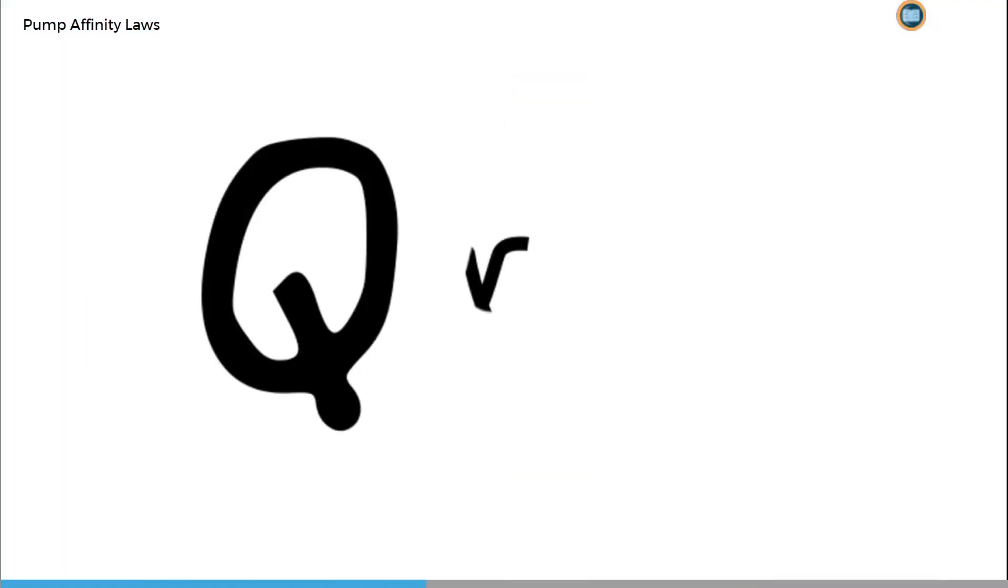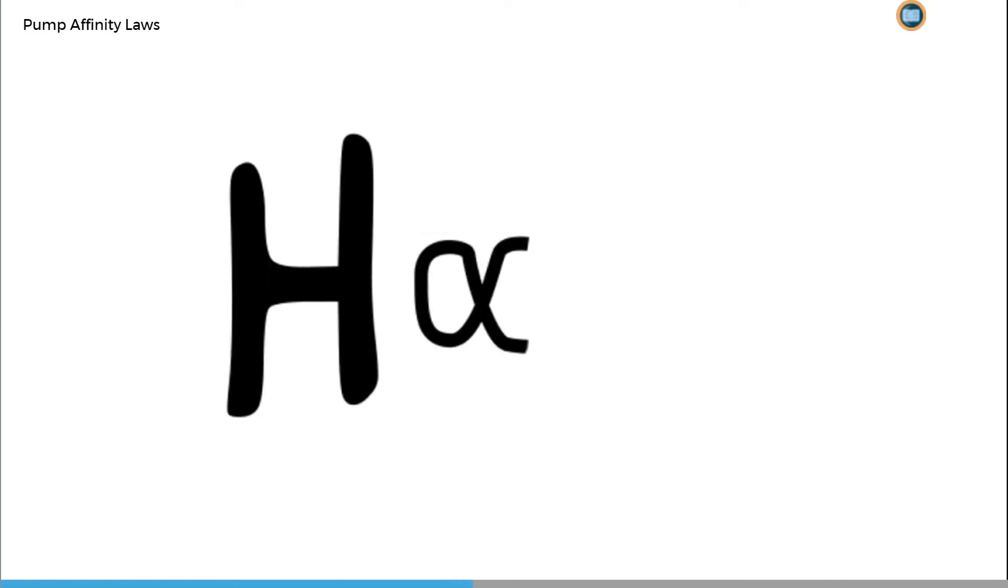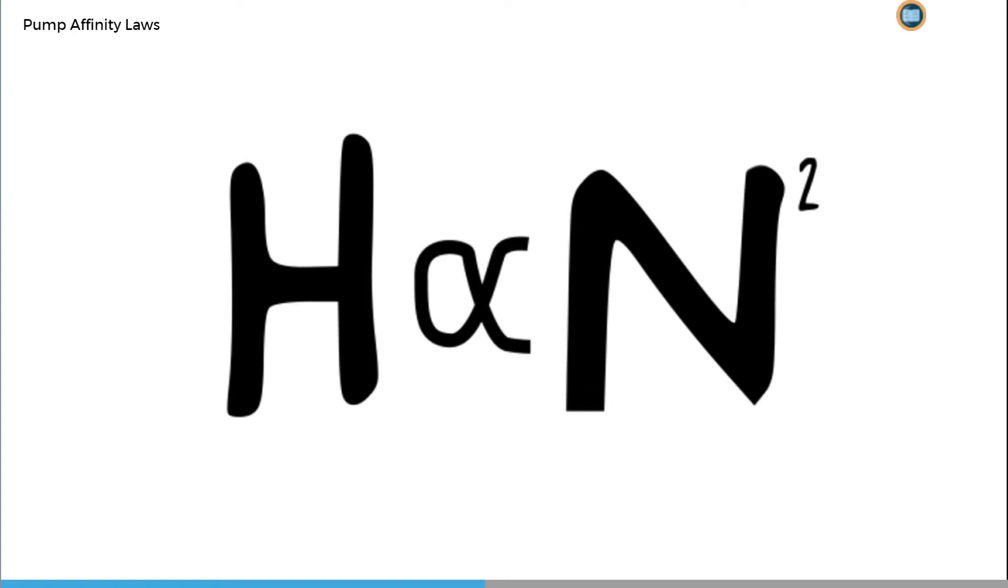One of these laws states that flow, Q, is directly proportional to the pump rotational speed, N, and another states that head, H, is directly proportional to the square of the pump rotational speed.